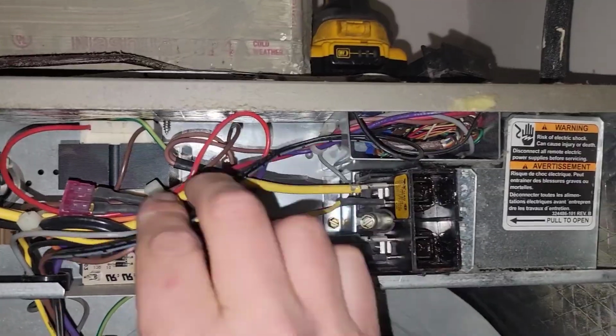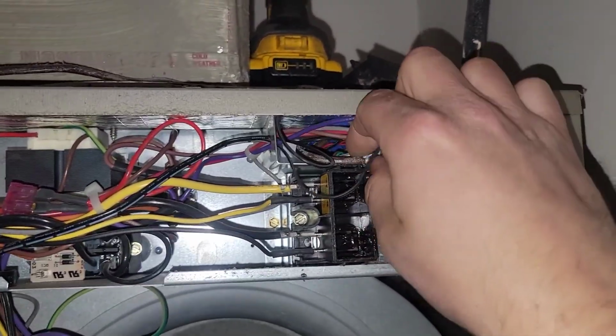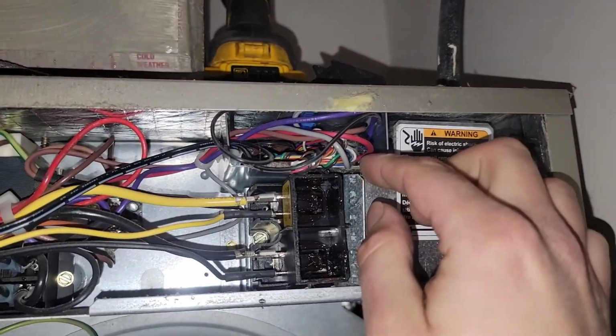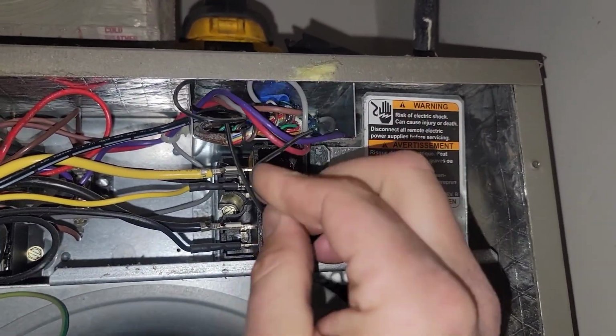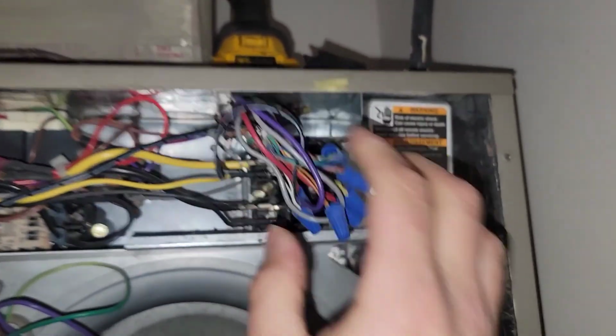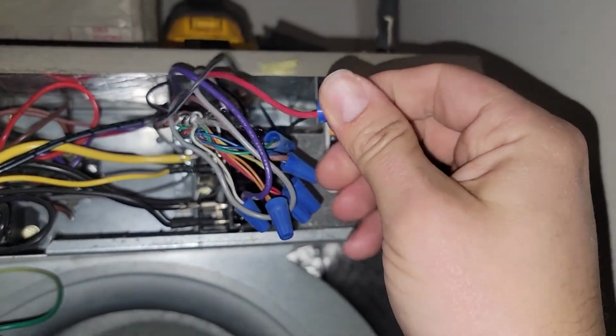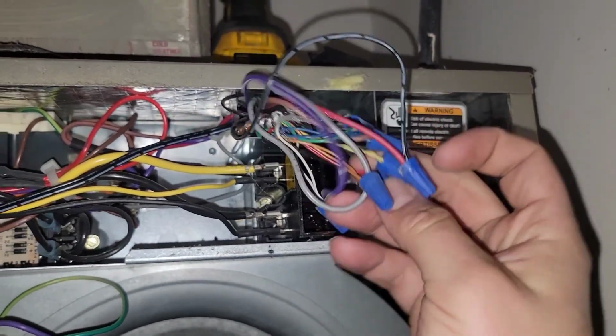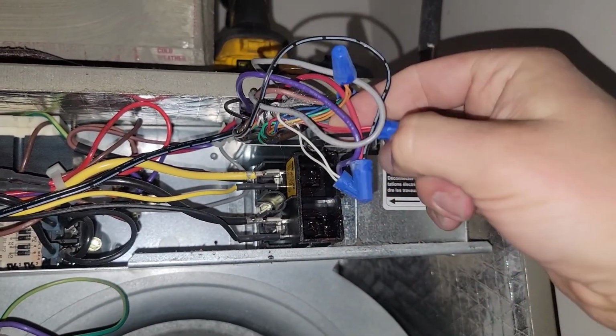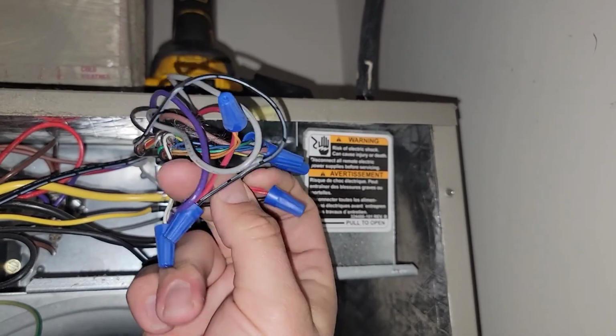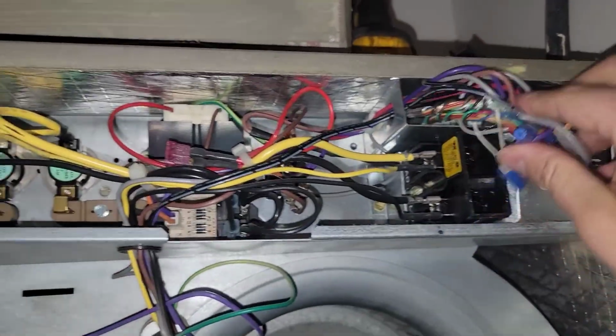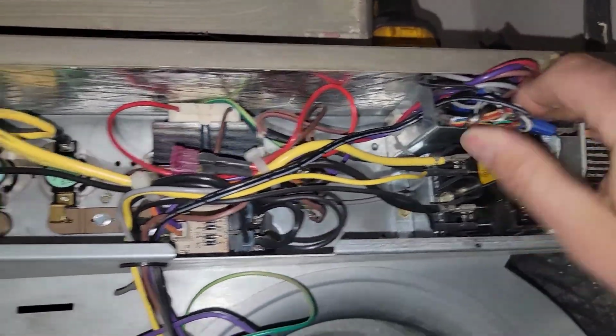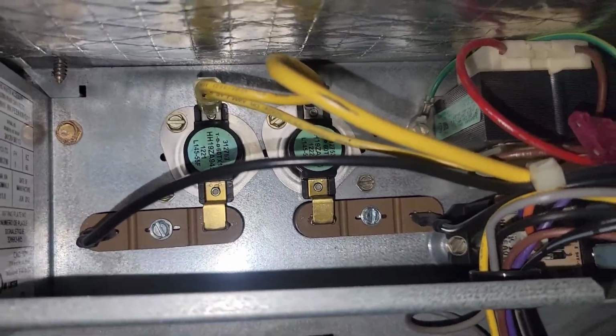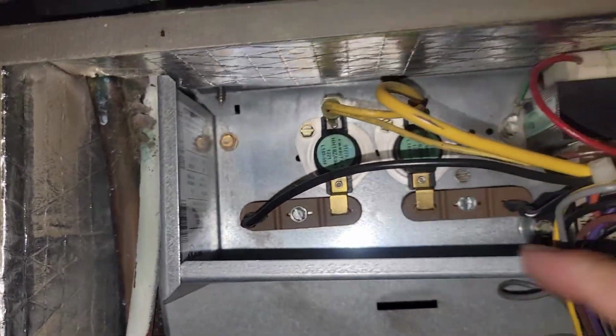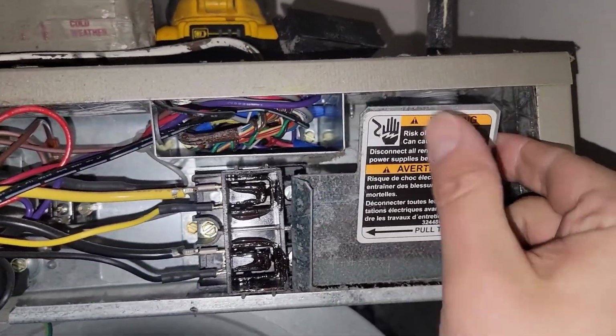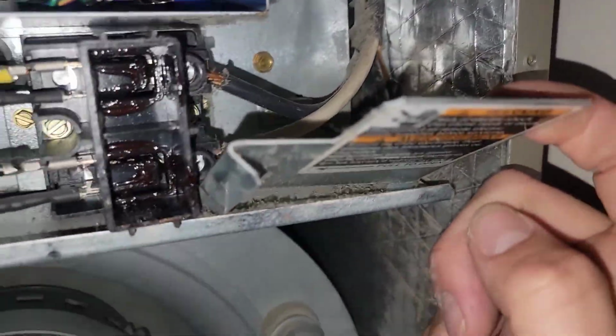Because you can see this comes up here, and I guarantee you it breaks the R, the red going to the thermostat. You can see, if I can get this big old bundle of wires out here, one wire goes to the red, which goes to the transformer, and the other, the black, you can see it right here, goes to the thermostat wires that go to the thermostat. So that's how they've got that wired. So yeah, looks like 10 kW. We got 2 heaters, 5K a piece. Those are the limit switches. And this is the wire coming in. Looks like number 6 wire.